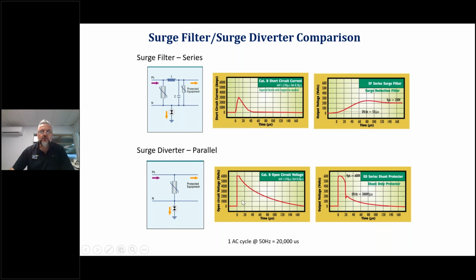So if we install the surge diverter, this would be the graph, or what would happen. If you have a surge diverter installed at your charger, the surge will be reduced to 600 volts, still quite an achievement from 6,000 volts to 600 volts. But the thing is, a surge diverter will do nothing for this fast rise time of voltage curve that you can see, and your equipment will still see that surge. And this is what we call dV/dt.